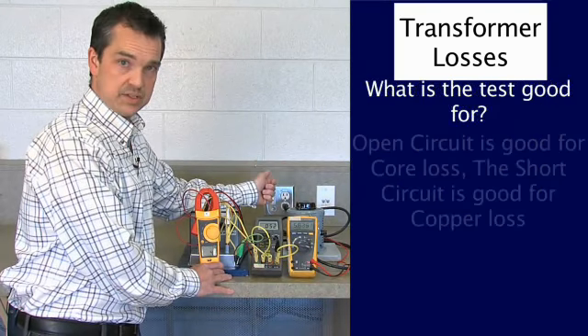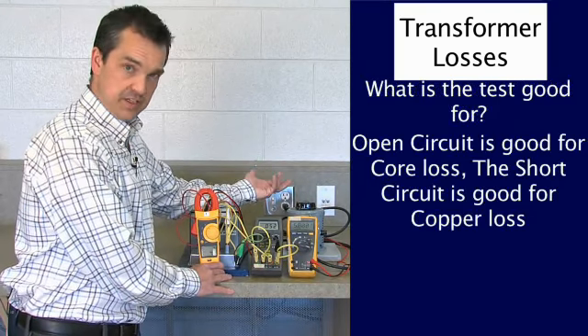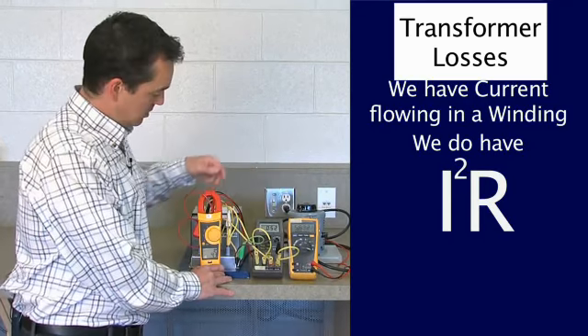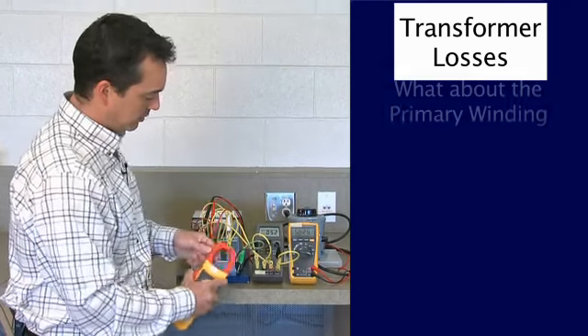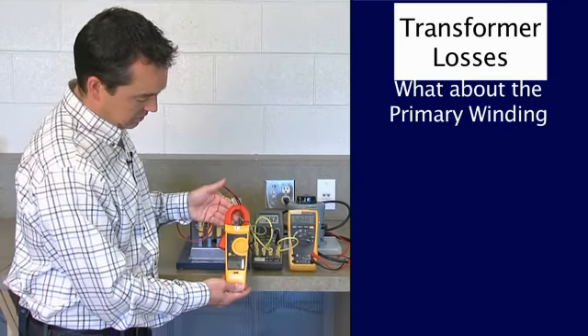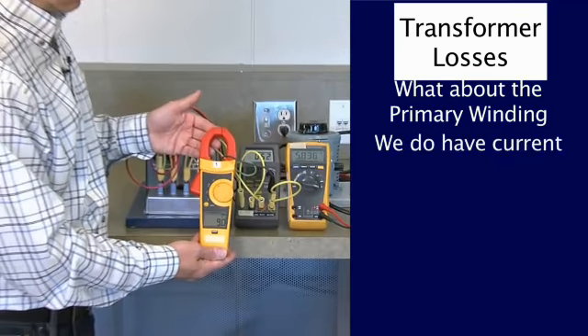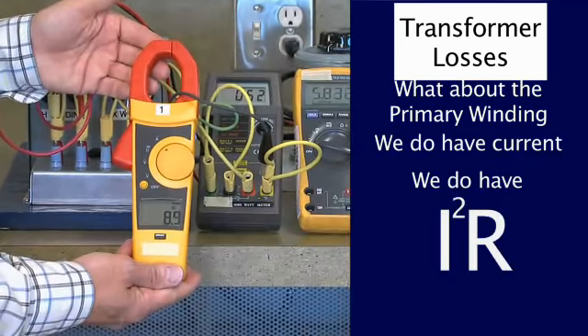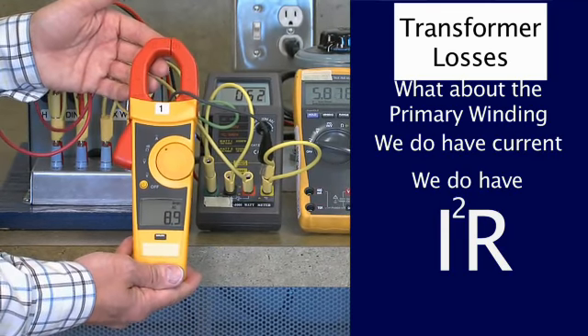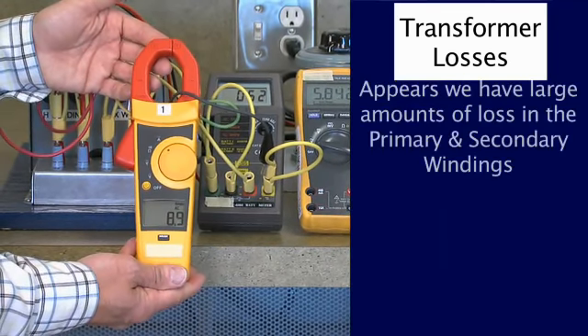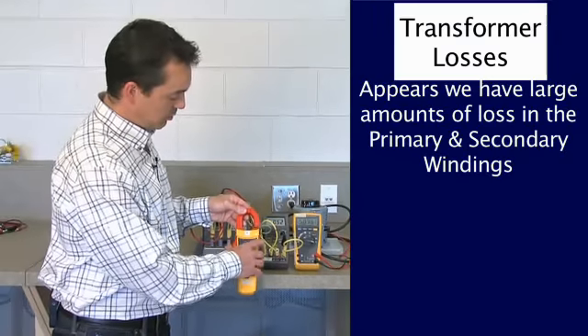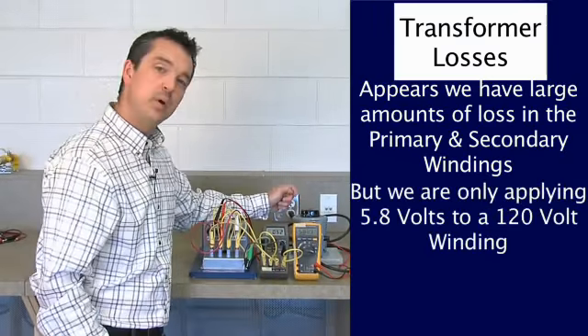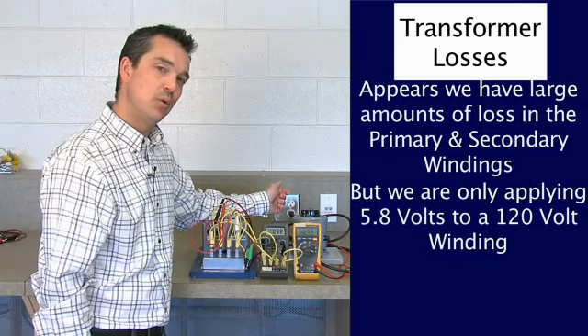Well, if the open circuit test was good for core loss, it would make sense that the short circuit is good for copper. Well, I have current flowing in a winding. I therefore have I squared R. What about the primary winding? Again, I have a bunch of current there. You're going to have I squared R. So it appears that I have lots of power loss in my primary and secondary windings, but I'm only applying 5.8 volts to 120 volt winding here.